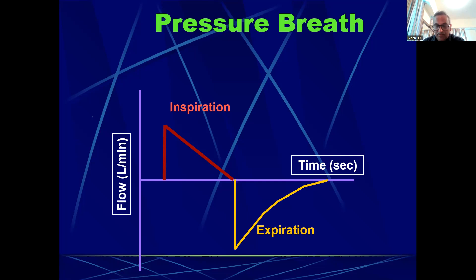Now, the different phases of a breath. What happens during different phases of a breath on a ventilator? This is inspiration, as I showed you, and this is exhalation. Certain basic terminologies I would like to explain. From the beginning of one inspiration to the beginning of the next inspiration, the whole thing is called the total cycle time. For example, if I am breathing at 20 per minute, that is 20 per 60 seconds, my total cycle time will be 3 seconds, because every 3 seconds I'm taking a breath. In that, this is the time spent in inspiration, the inspiratory time, and this is the expiratory time. So basically your total cycle time is inspiratory time plus expiratory time.